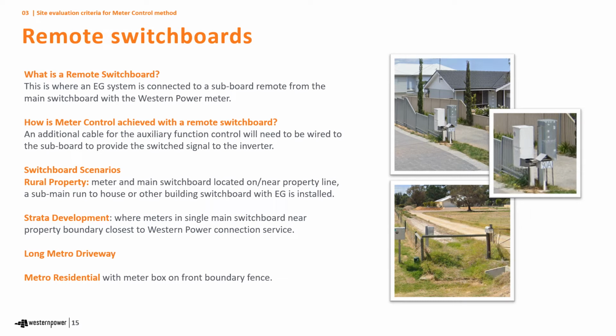Now, remote switchboards. What is a remote switchboard? This is where an inverter system is connected to a subboard remote from the main switchboard with the Western Power meter. And to get the control signal from the meter to the remote switchboard, you'll need to put an additional cable for the auxiliary function control and wire it all the way back to the subboard. And this provides a switch signal to the inverter.